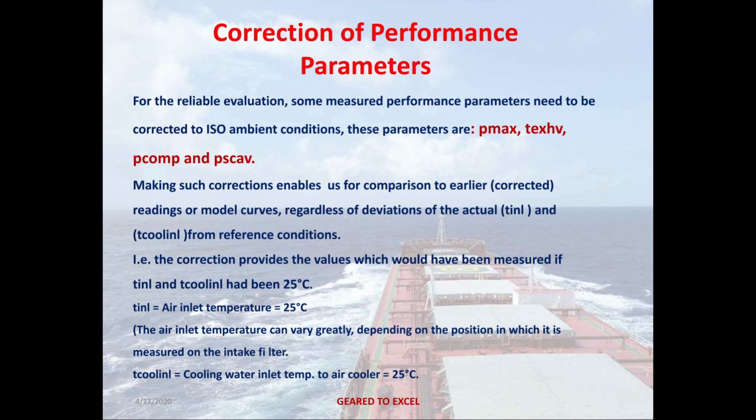That is, the correction provides the values which would have been measured if the air inlet temperature and the cooling water inlet temperature had been 25 degrees Celsius. The air inlet temperature is equal to 25 degrees centigrade. The air inlet temperature can vary greatly depending on the position in which it is measured on the intake filter. T-cool in is the cooling water inlet temperature to the air cooler at 25 degrees Celsius.